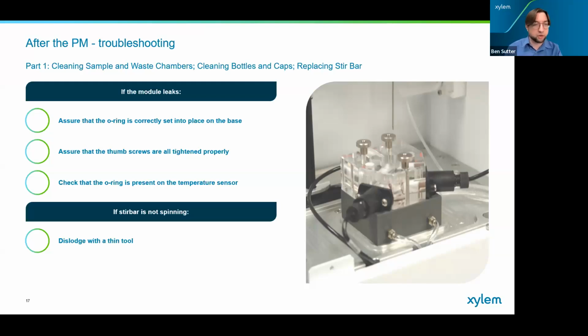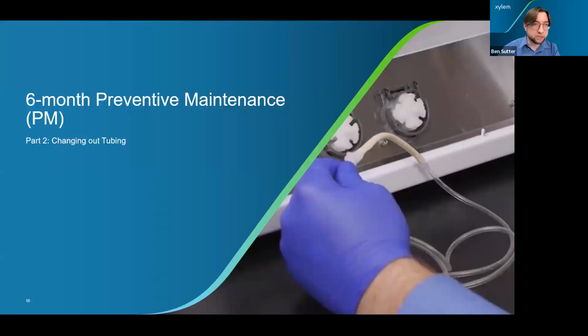Sometimes, for whatever reason, sugar or salts or other biological matter collects at the bottom of the sample chamber, and sometimes it can be glued there. That is, the little tiny stir bar can be glued to the bottom. You just need to get in there with a thin tool, dislodge it, and it will work just fine afterwards. Those are my follow-on tips. Next thing we're going to talk about is changing out the tubing, which is one of the most important parts, in my opinion, of the PM. I'm going to send it back over to Jason, and I'll let you take care of it.